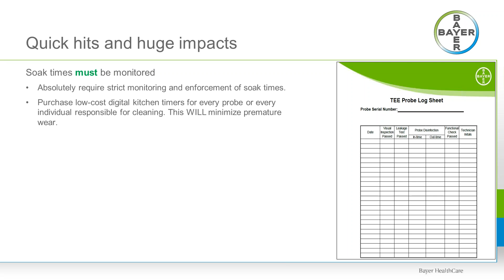Some type of tip protection, again, should be in place anytime the probe is not within the patient. Single-use options are available from many sources, including Bayer Multi-Vendor Service. We do sell our tip protectors, as well as provide them on all of our repaired and loaner products. Some customers have really sought out a no-cost solution. What they've done is wrap the tip of the TEE probe with a quarter-folded washcloth, and if they do have to hold it in place, they wrap it with a rubber band.